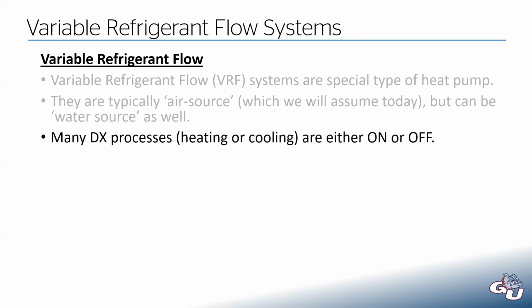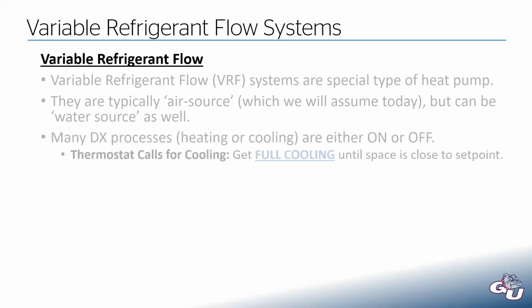Most DX processes, so any process that's a direct expansion refrigerant-based process, whether that's heating or cooling, are either an on or off type of system. It's a binary kind of system where the system is either on or it's off. So when your thermostat says, hey, we're getting warm in here, that sends a signal to your air conditioner that says, I want cooling. And when that system turns on, you just get full-blown cooling.